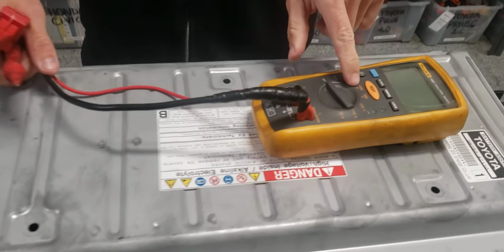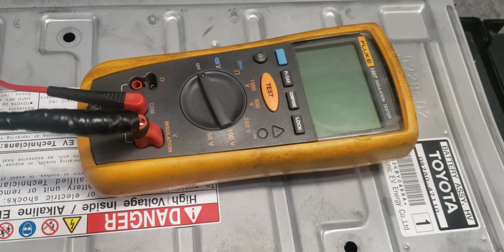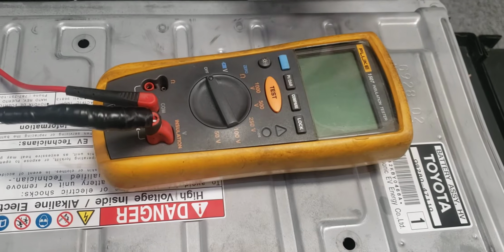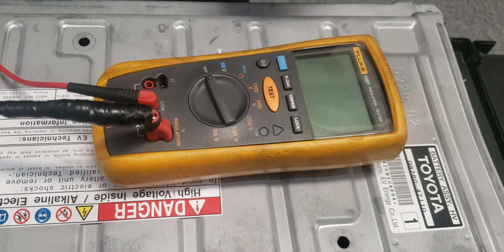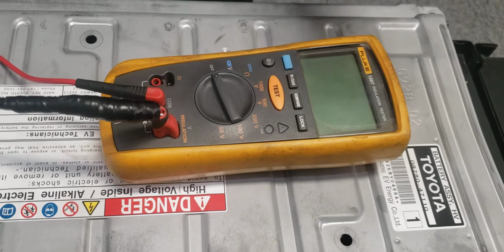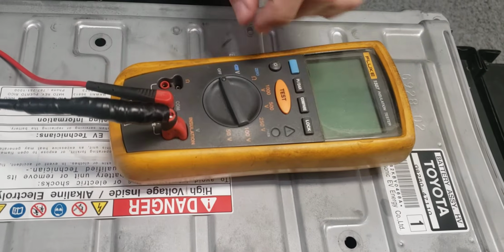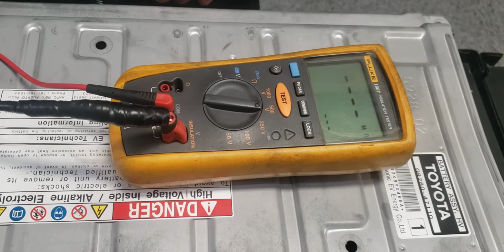First thing, you need your insulation tester or mega ohm meter, and I'll show you how to set it up. There are multiple selections: 1,000, 500, 250, 100. So what voltage range do you choose? You want to do double the battery voltage, doesn't have to be exact. This one's a little over 200 volts, so we're going to go to 500.